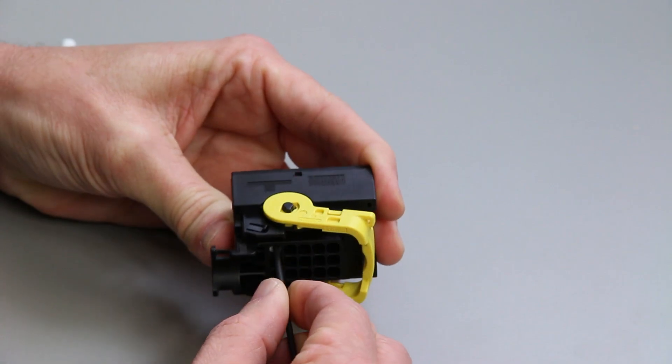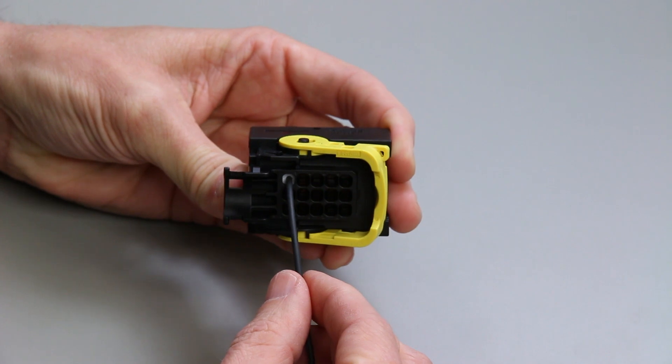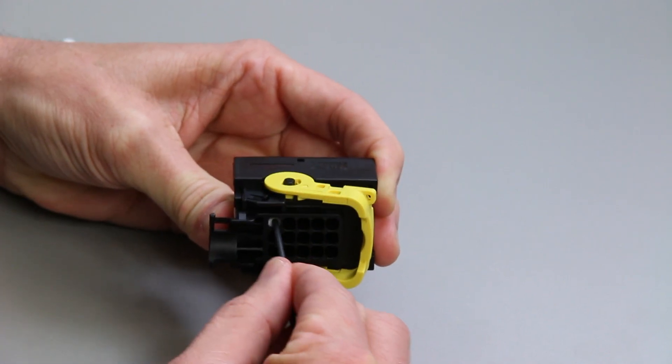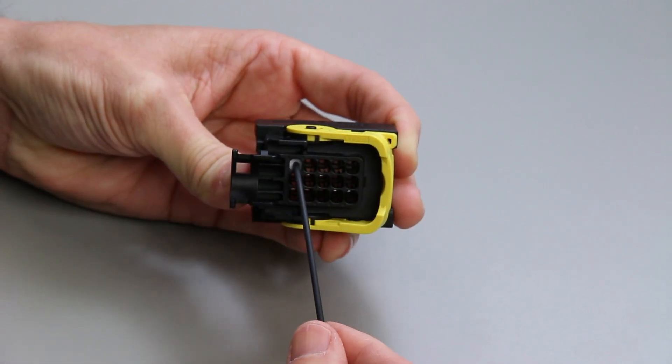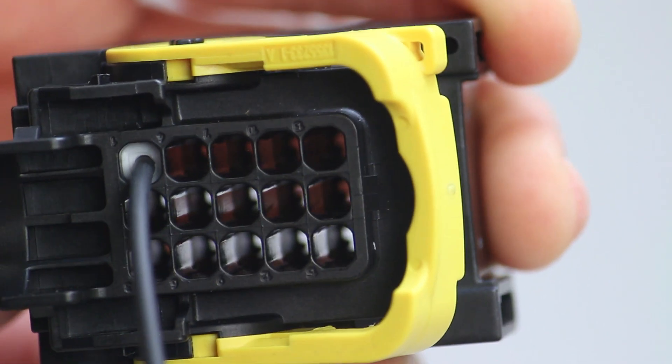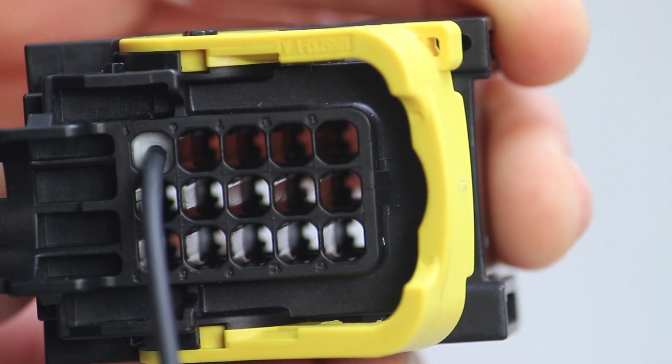Push the contact straight into the rear of the connector until you hear and feel a click. A slight tug will verify the contact is locked in place. Repeat this process until all of the cavities are filled.